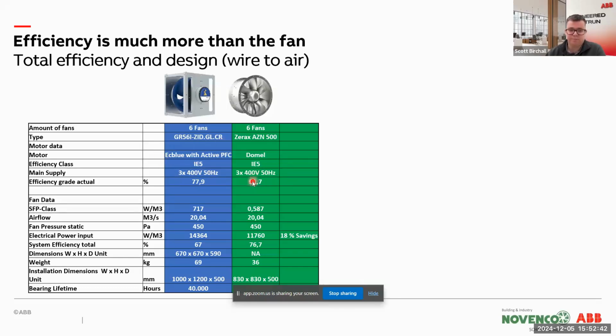These systems are equal. So what they did is look at comparable airflow: they're both 20.04 cubic meters per second, and the static pressure as well, 450 pascals. Just to balance it out and show these are like-for-like comparisons, the pressure and flow was maintained on both. So for the electrical power input, you can see there's an 18% reduction using the axial fan option compared to the ECM combined package. And the system total efficiency, which is again what we're really interested in, is 76.7 compared to 67%. This is where you can really understand how efficient a system is, because these numbers don't lie.